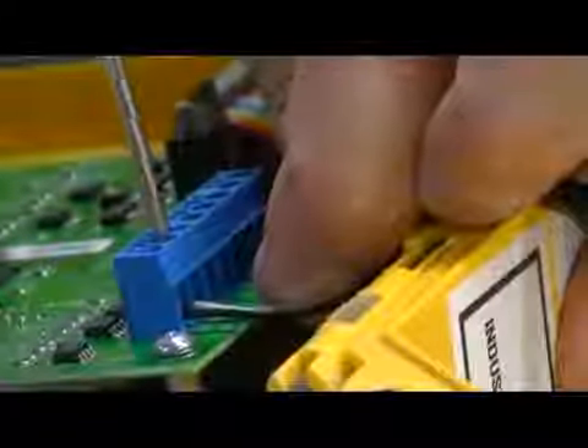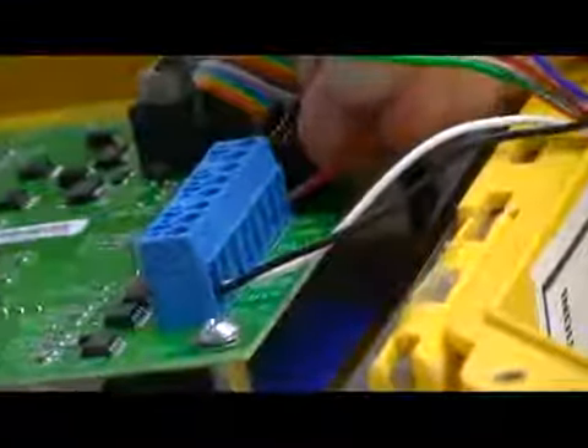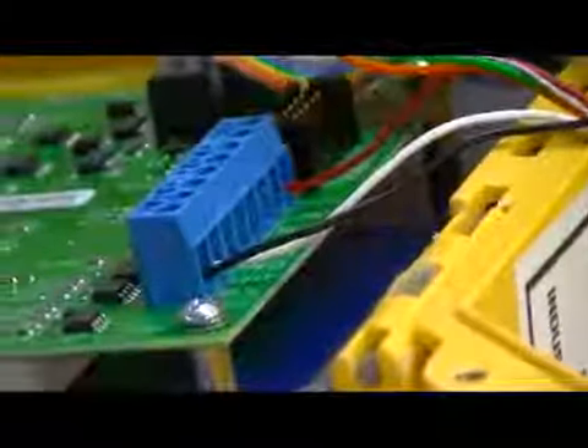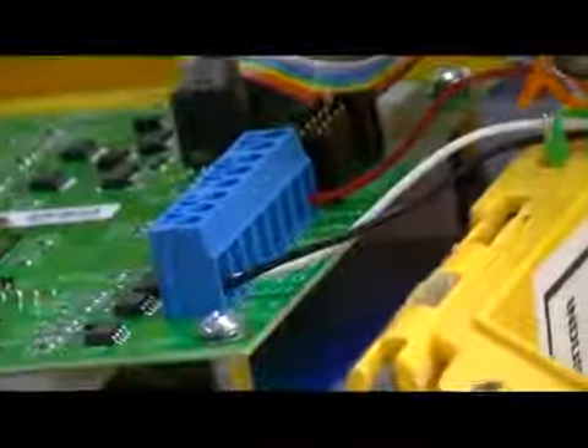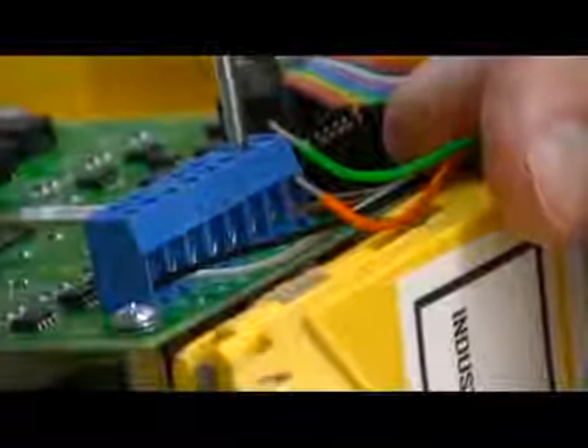The only color that changes is the red wire now wires in to the REM terminal on top. We up the voltage for remote sensor applications, and that red wire needs to be wired on that terminal. The other thing that changes is that we do use a shield on a remote sensor that needs to be grounded on the ground terminal. Again, just following the color code.